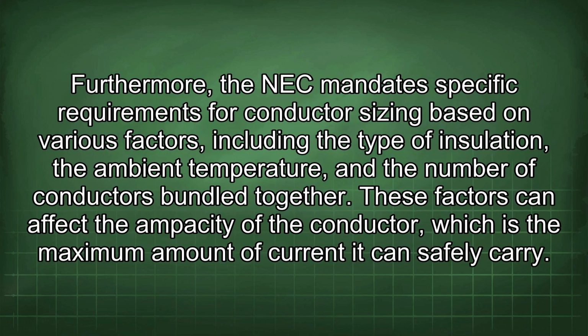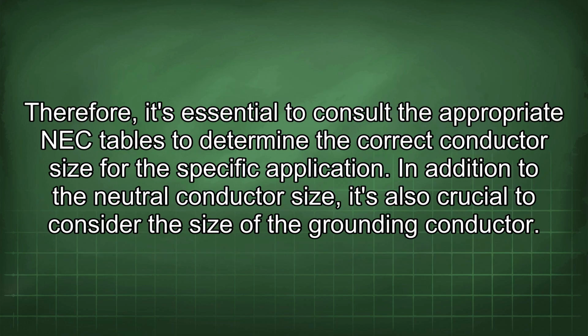Furthermore, the NEC mandates specific requirements for conductor sizing based on various factors, including the type of insulation, the ambient temperature, and the number of conductors bundled together. These factors can affect the ampacity of the conductor, which is the maximum amount of current it can safely carry. Therefore, it's essential to consult the appropriate NEC tables to determine the correct conductor size for the specific application.